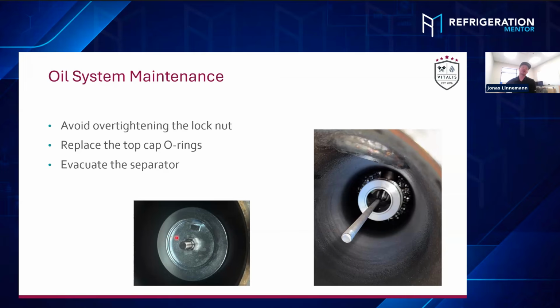Yeah, it depends on what, like I've seen different nuts being used for different oil separators. Sometimes it's these mechanical metal lock nuts. They already need such a strong torque to just spin them down. It's very hard to say when they really start to push on the top cap and when you're just rotating. So the easiest is to just screw it down slowly, touch the cartridge, and you will feel as soon as it's not sloppy anymore. Give it a little extra spin and that's it. Perfect.